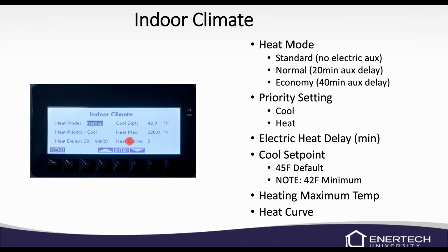Indoor climate, again, it will tell you whether we're in normal mode, standard mode, or economy mode. Standard's no electric auxiliary, normal's 20-minute delay, economy is 40-minute delay. You can set your priority setting, whether that's cooling or heating, and we're talking about hydronic heating, not domestic, obviously. You can set your electric heat delay in minutes. If these 20 and 40-minute don't work for you, you can set a different delay.